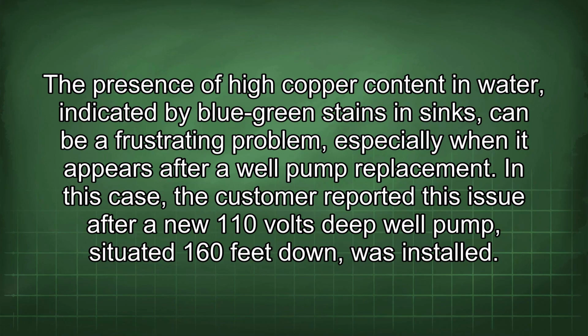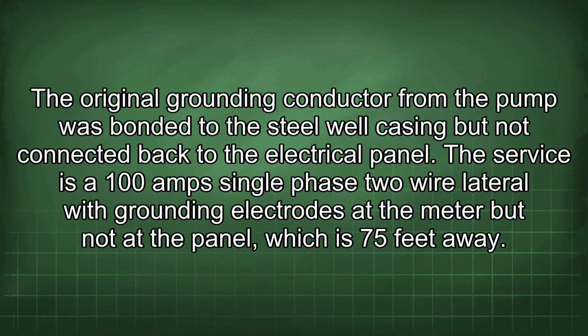The presence of high copper content in water, indicated by blue-green stains in sinks, can be a frustrating problem, especially when it appears after a well pump replacement. In this case, the customer reported this issue after a new 110 volts deep well pump, situated 160 feet down, was installed. The original grounding conductor from the pump was bonded to the steel well casing, but not connected back to the electrical panel. The service is a 100 amp single-phase 2-wire lateral with grounding electrodes at the meter but not at the panel, which is 75 feet away.